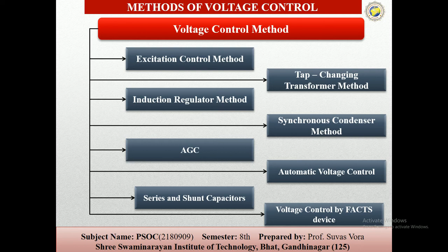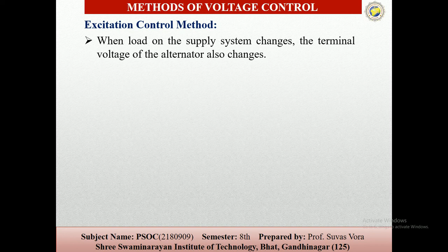Now the excitation control method. When the load on the supply system changes, the terminal voltage of the alternator also changes. This alternator voltage is kept constant by changing the field current of the alternator according to the load. The field current is also called the excitation current, therefore this method is called excitation control. Simply, in a motor we provide excitation from outside. In a similar way, this is the excitation control method.